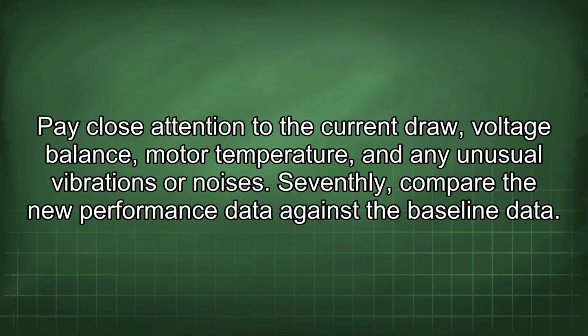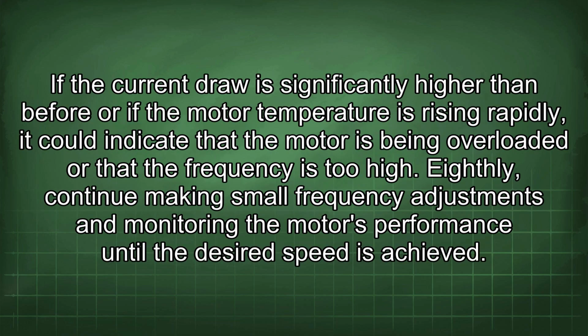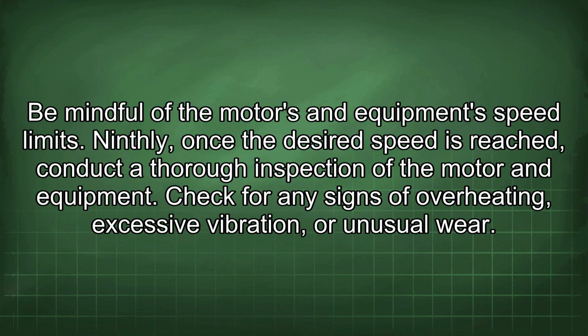Seventhly, compare the new performance data against the baseline data. If the current draw is significantly higher than before, or if the motor temperature is rising rapidly, it could indicate that the motor is being overloaded or that the frequency is too high. Eighthly, continue making small frequency adjustments and monitoring the motor's performance until the desired speed is achieved. Be mindful of the motor's and equipment's speed limits.